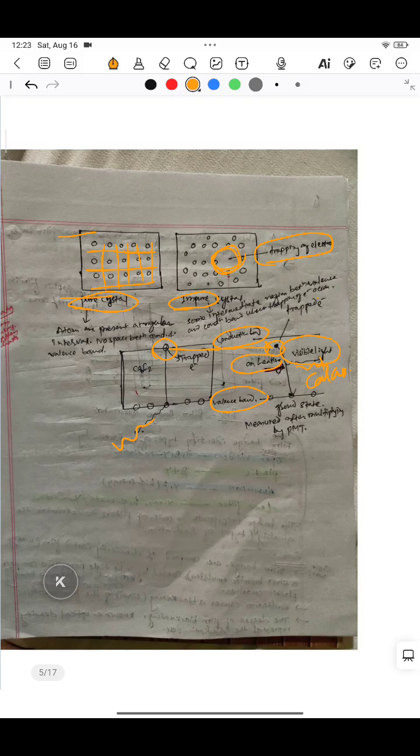The electron had gone from the ground state to the higher state, or lower energy state to the higher energy state. By releasing light it comes back to the ground state, and the light is measured by the photomultiplier tube. So by measuring with the PMT tube we can calibrate the amount of radiation dose.